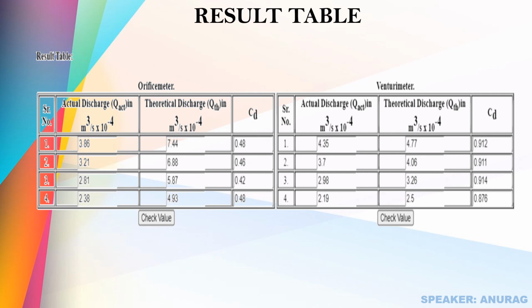But for the Venturi meter, for the last observation of pressure difference of 16 mmHg, we can see that there is a large variation in coefficient of discharge, because for the Venturi meter the accuracy for a small pressure difference is low. That's why we use orifice meter for small changes in pressure values.